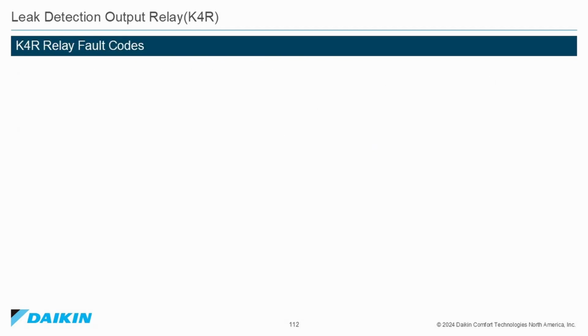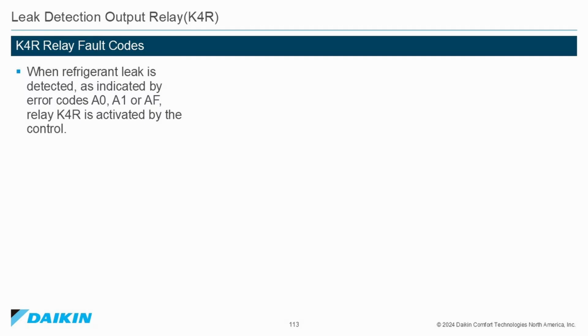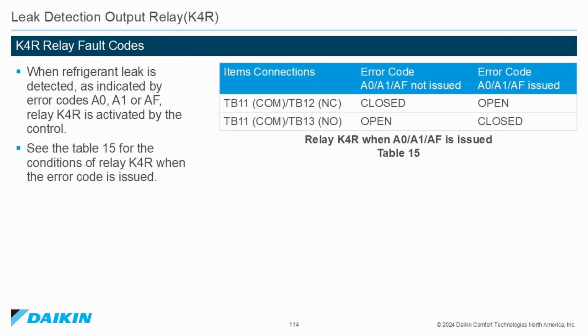K4R relay fault codes. When a refrigerant leak is detected, as indicated by error codes A0, A1, or AF, relay K4R is activated by the control. See Table 15 to the right for the conditions of relay K4R when the error code is issued. Terminal blocks 11 and 12 are closed if there is no error code, and they are open if there is an error code issued. Terminal blocks 11 and 13 are open if there's no error code, and closed when an error code is issued.